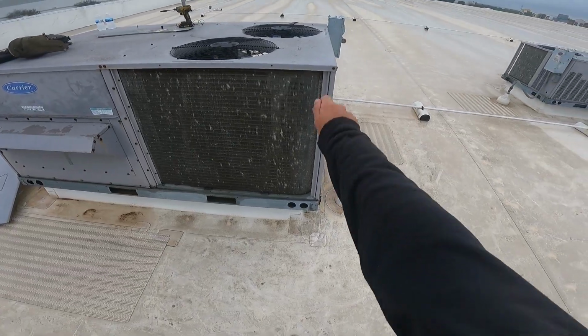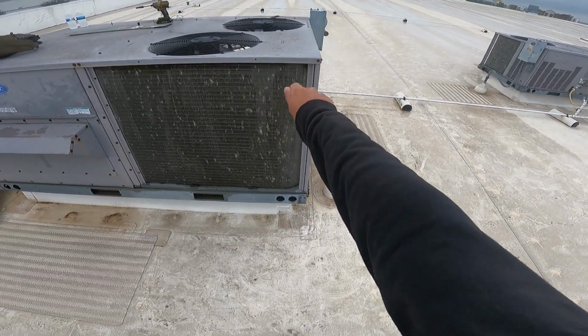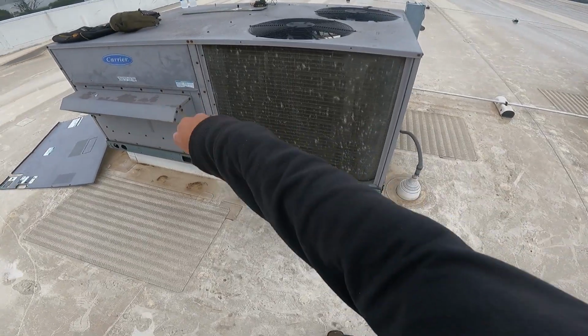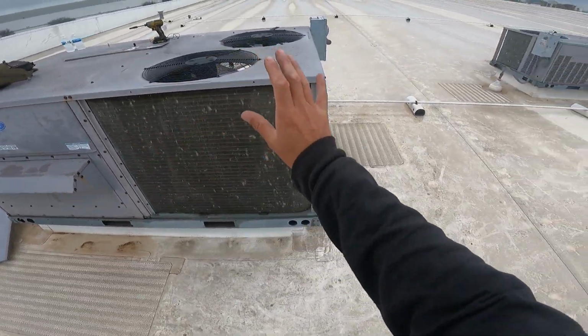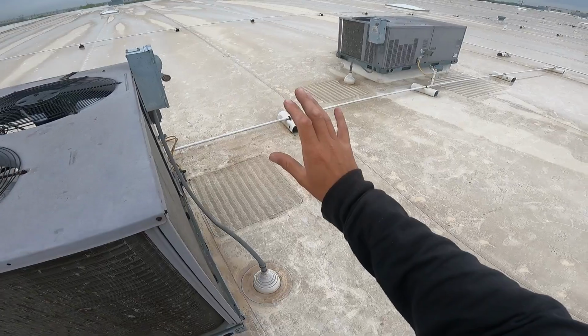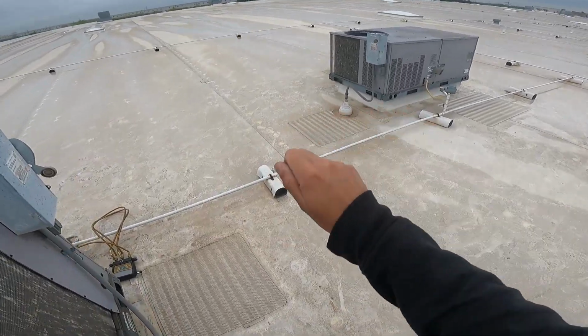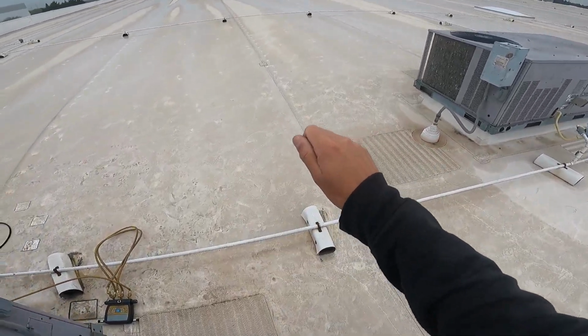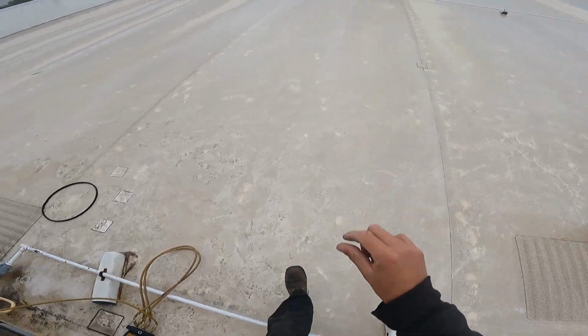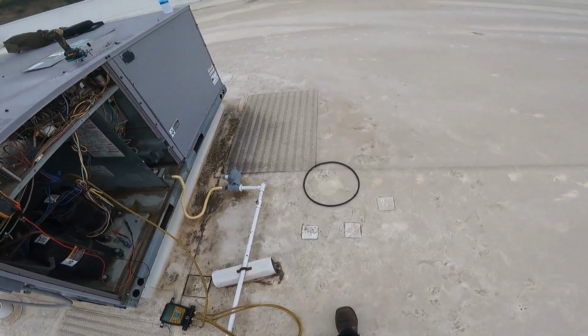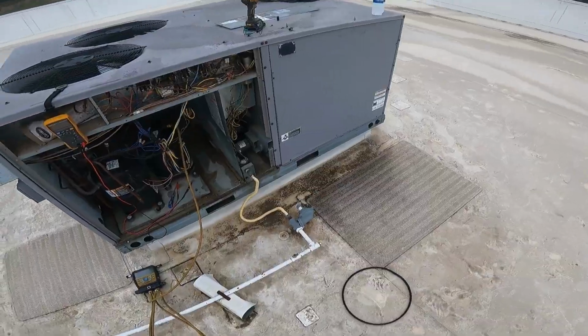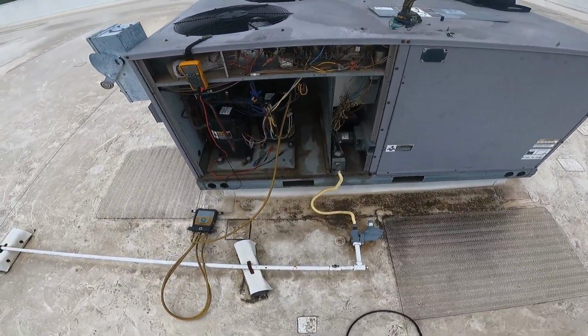You just gotta burn the fins away, wherever the leak is. If it's in the evaporator, just burn the fins away — low flame, low heat, and patience. Once you get it all cleaned up and see where you're spewing, get in there and braze it right on up.